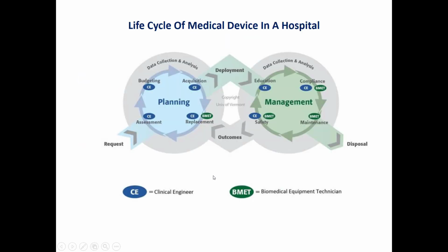engineering department. Prior to starting with the policies and the procedures, we can see in this figure the life cycle of a typical medical device in a clinic in a hospital. The life cycle starts with a request from a medical department, and ends with the disposal of this equipment. It can be separated into two main parts, the planning part and the management part.